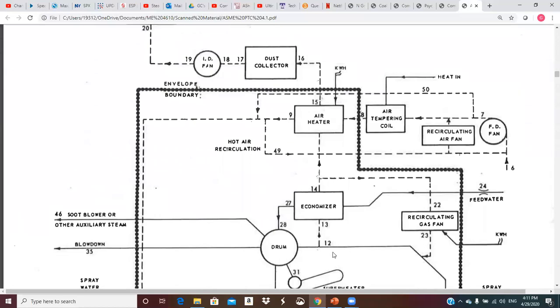So here's my flue gas exiting at 12, coming into the economizer at 13, probably pretty close to the same state. Then it dumps off heat to the feed water coming in, in the economizer, comes out. So here's my flue gas recirculation fan. I got this one confused with this one a minute ago. So if we're doing flue gas recirculation, we can do this for at least two reasons. We can do it for some steam temperature control. We can also do it to limit NOx emissions. If you pull some of this off, put it back in here, it gives any NOx in here a chance to be destroyed by going back into the furnace.